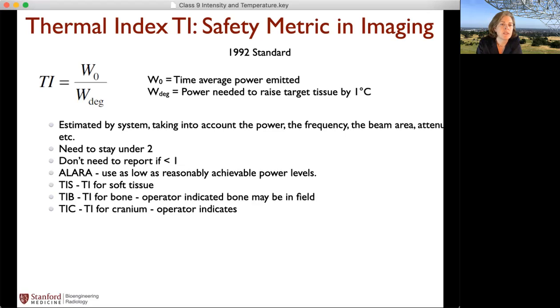So essentially, if you put in enough power that's going to raise it by 1 degree C, then you get a TI of 1. If you put in twice that, you'll get a TI of 2. So it's going to take into account the power, the frequency, the beam area, the attenuation, et cetera. And the FDA says they need to stay under 2. They don't actually need to report it if it's less than 1, but I'll show you some images in just a moment where it is reported on the commercial ultrasound system.